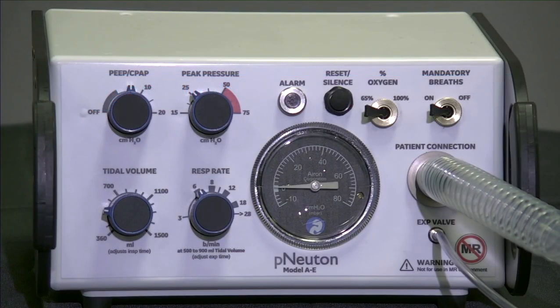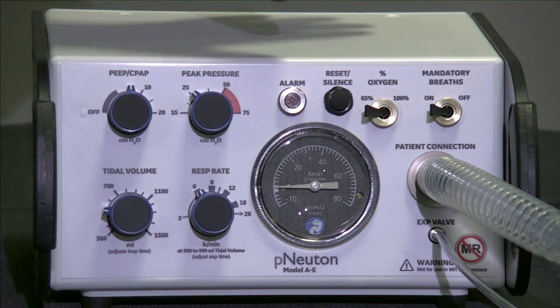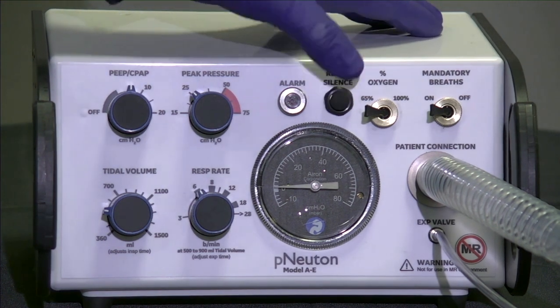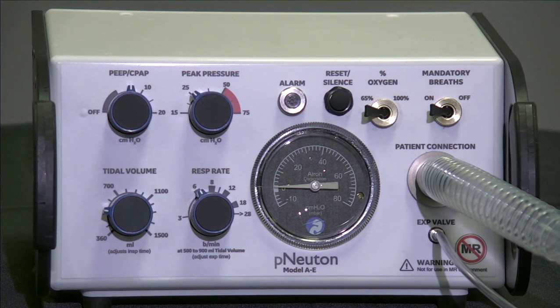Let's take a look at the operation of the pNeuton A-E ventilator. When we first turn on the gas, the ventilator will alarm. Press the reset silence button to silence the alarm for 1 minute. The alarm is set to sound after 20 seconds if no mandatory breath is delivered with a minimum of 15 centimeters of water pressure, if CPAP is set less than 4 centimeters of water, or if there is a loss of gas supply.